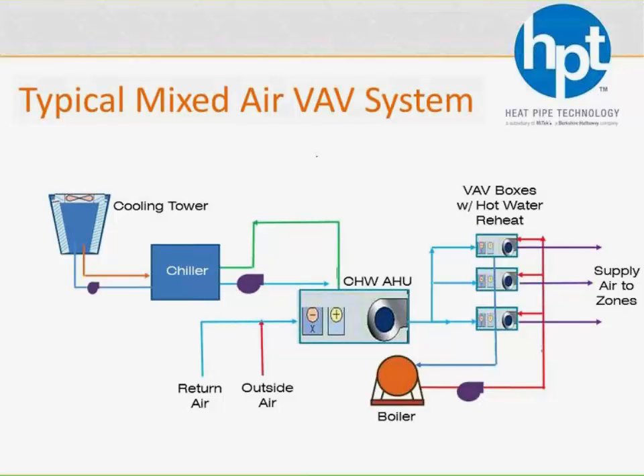So here's an example of your conventional mixed air system. This one's using VAV boxes. It's also using chilled water. It could be DX. But the bottom line here, if we're talking mixed air, then the return air and the outside air is being mixed upstream of the cooling coil. So the cooling coil is seeing that mixed air, ventilation and return, and dehumidifying it as a whole, and then delivering that air out to the space where some kind of air terminal unit, in this case a VAV box, is going to deliver that air to each zone and then reheat it or vary the volume as necessary depending on the load in the space. Pretty common.